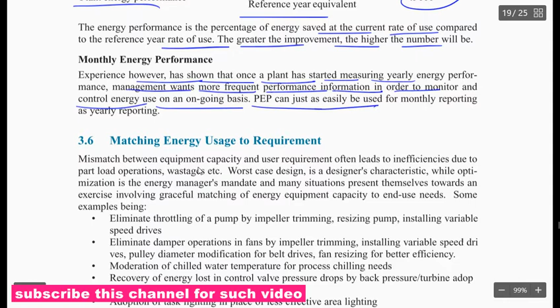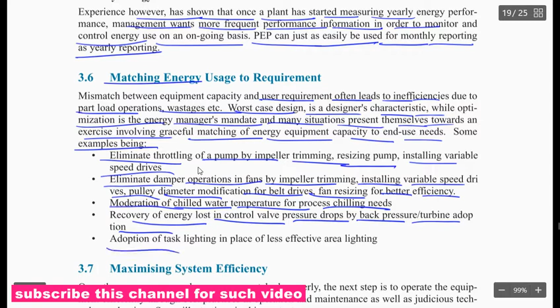Matching energy usage to requirement. Mismatch between the equipment capacity and user requirement often leads to inefficiency due to part load operation, wastage and worst case design. While optimizing energy management, many situations present themselves towards an exercise involving graceful matching of energy equipment capacity to end use need. Some examples: eliminate throttling of the pump by impeller trimming, resizing the pump and installing a variable speed drive; eliminate damper operation in fans by impeller trimming and installing variable speed drives; pulley diameter modification for belt drives; fan resizing for better efficiency; modulation of chilled water temperature for process chilling need; recovery of energy lost in control valve pressure drop by back pressure and turbine adoption; and adoption of task lighting in place of less effective area lighting.